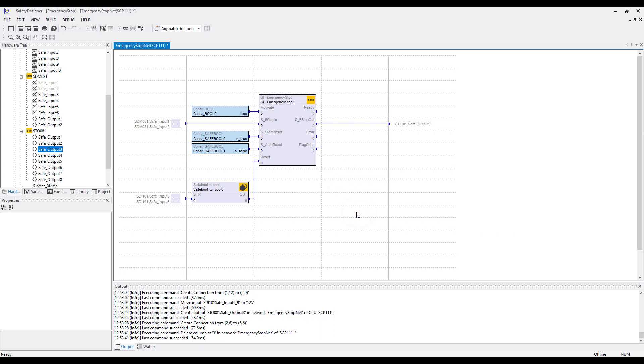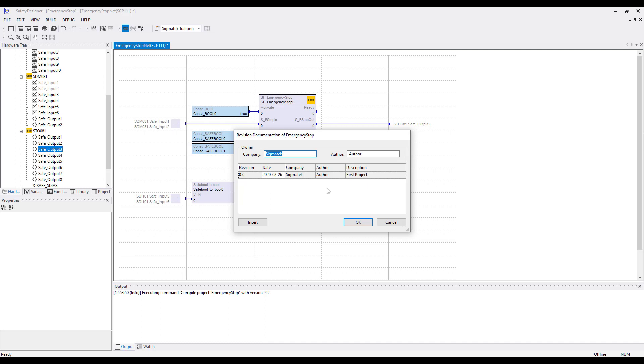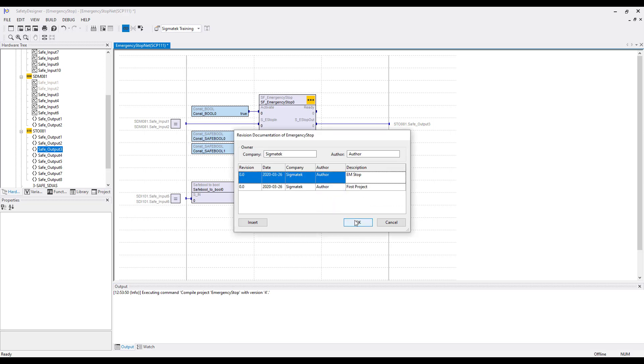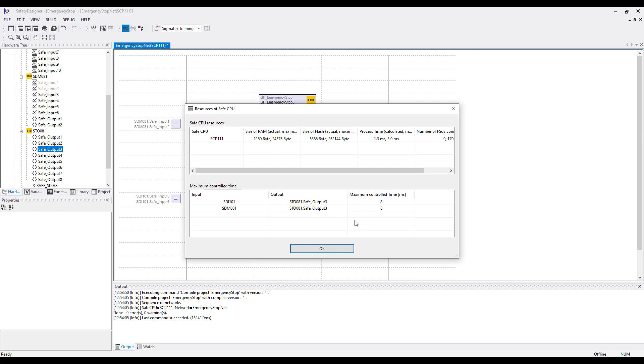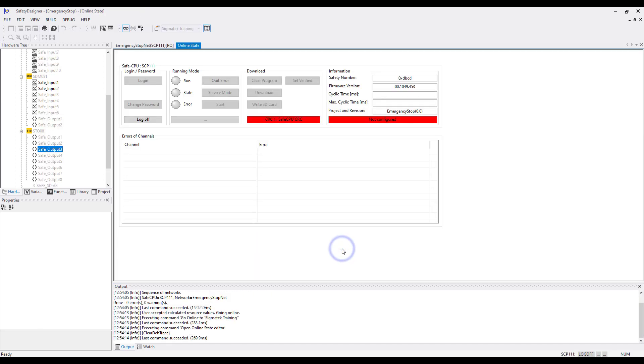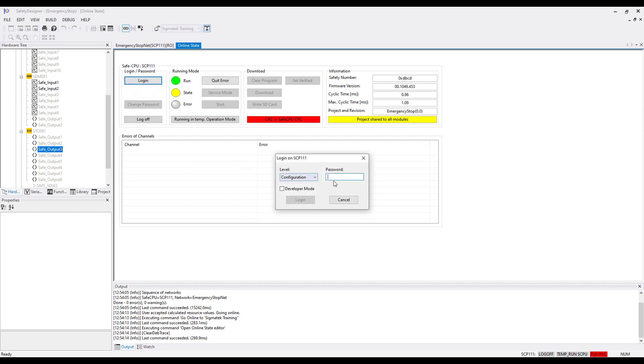Once everything is set up, you can go online. You get the revision documentation for Emergency Stop again. Insert a new entry and type in a new description, then press OK. Another window opens showing the resources of your safe CPU — click OK. Now we are in the online state window. You have to log in first, so click the Login button. The standard password is 123456. Once you have entered the password, click Login.